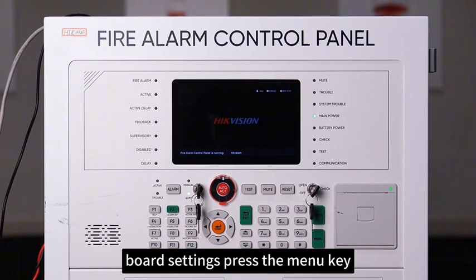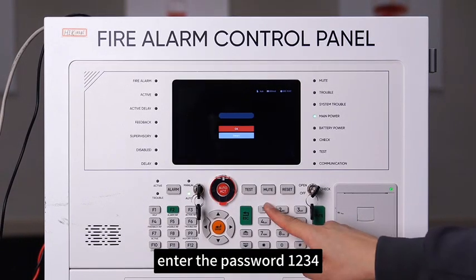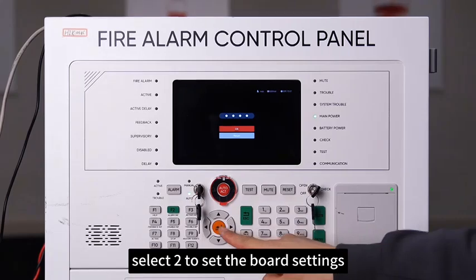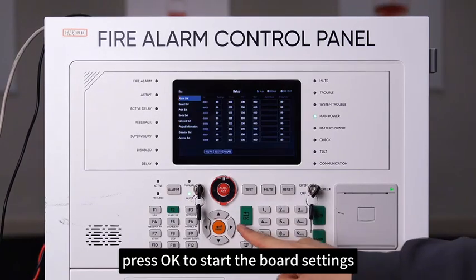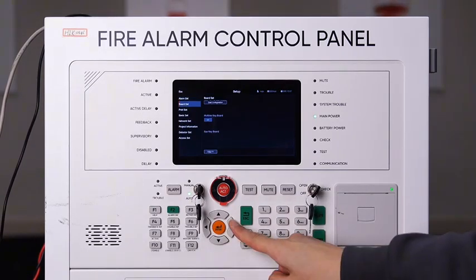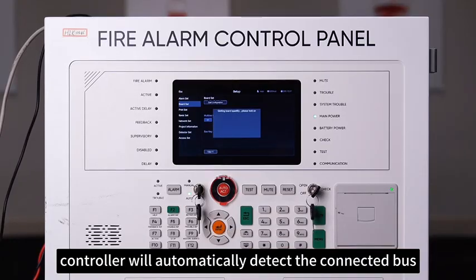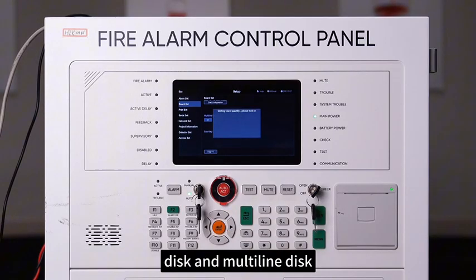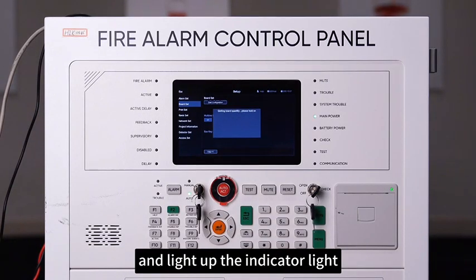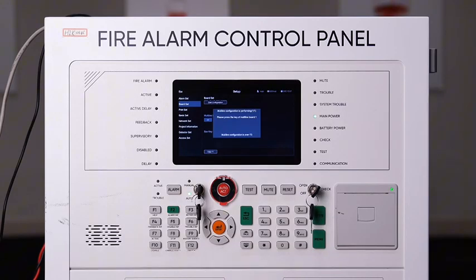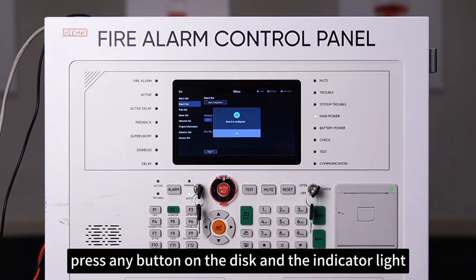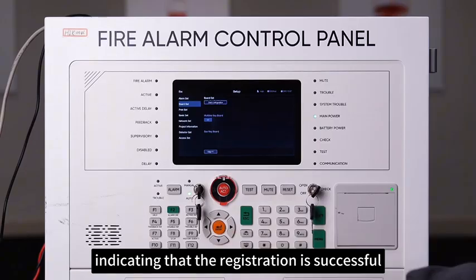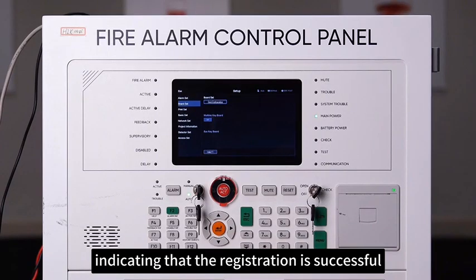Board settings, press the menu key, enter the password 1234, select 2 to set the board settings, press OK to start the board settings. At this time, the controller will automatically detect the connected bus disk and multi-line disk and light up the indicator light on the disk. Press any button on the disk and the indicator light will go out, indicating that the registration is successful.